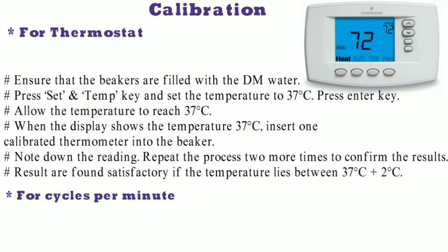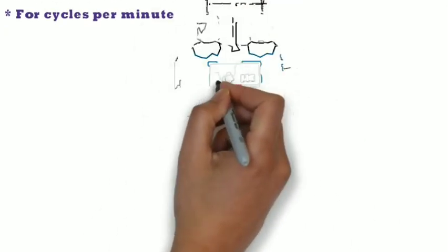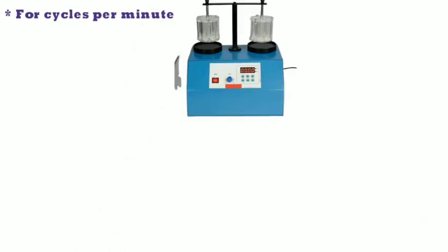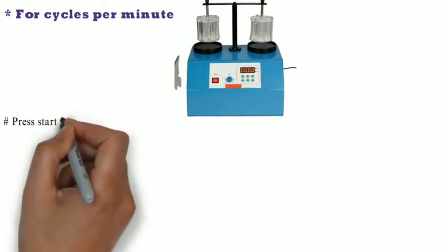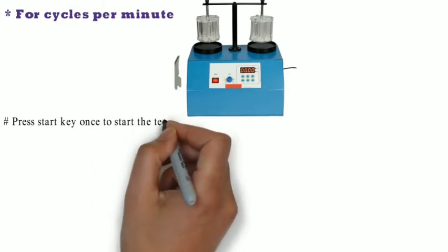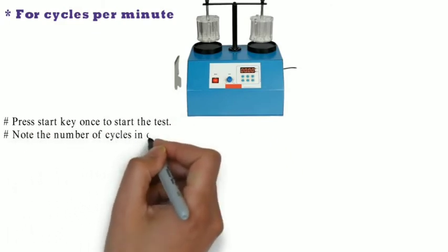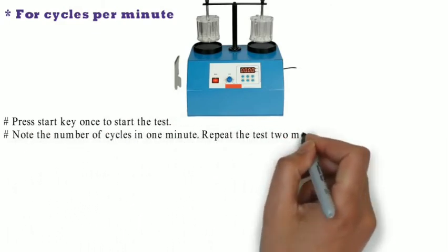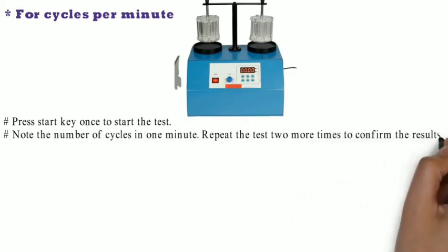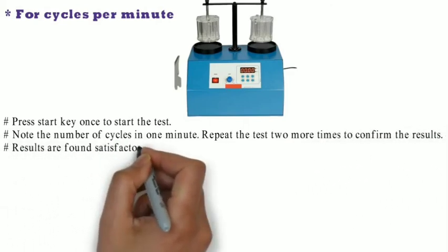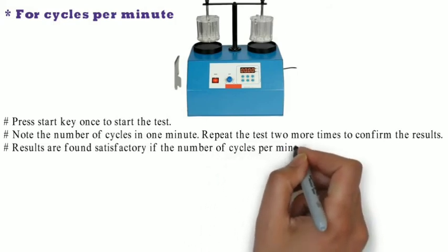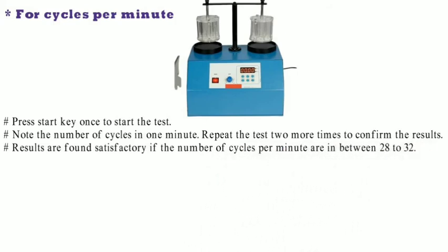For cycles per minute, this is the stroke, and this is the disintegration time. There are 2 types of strokes, as you can see there. Here, press the start key once to start the test. Note the number of cycles in 1 minute. Repeat the test 2 more times to confirm the results. Results are satisfactory if the number of cycles per minute is between 28 and 32.